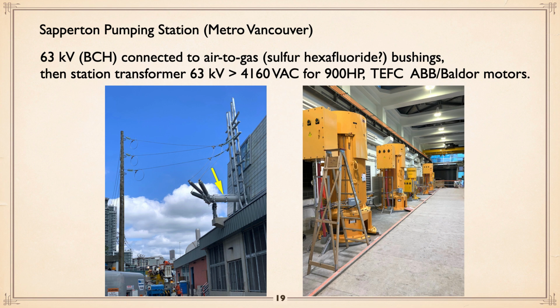Now, how do we prevent a short there? Because in that pipe is not air. There's a gas with a higher resistance to shorting than air, likely sulfur hexafluoride, okay? And the transformer then takes that power coming in and transforms it from 63 kV, 63,000 volt, to 4160 volt to power these 900 horse TEFC. We'll get later into what that means. ABB Baldor. Baldor was a good company in Fort Smith, Arkansas that was bought out by ABB out of Europe. So just a little point of interest, okay? Moving right along.